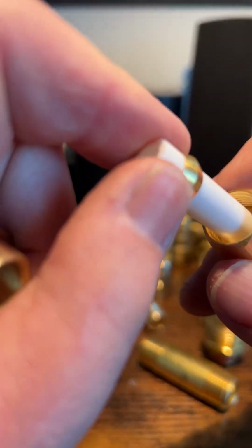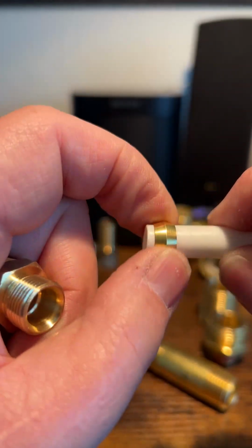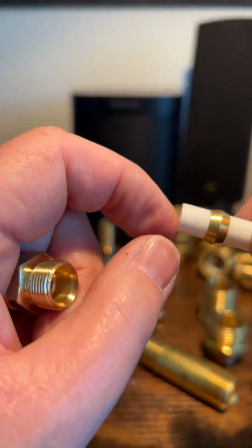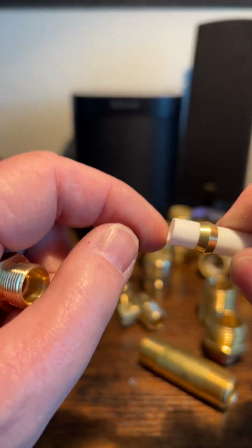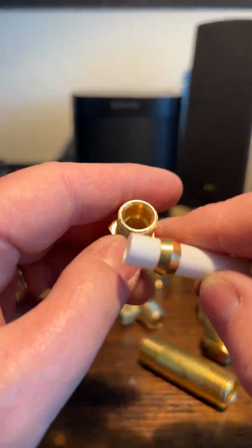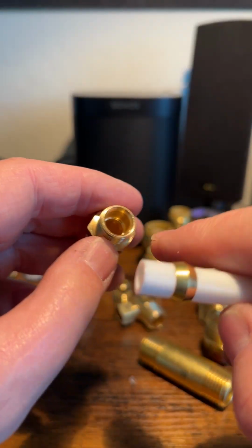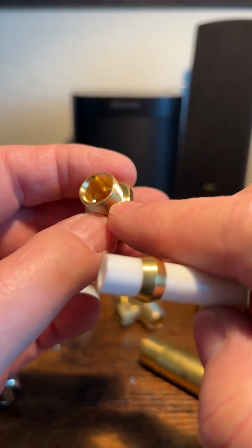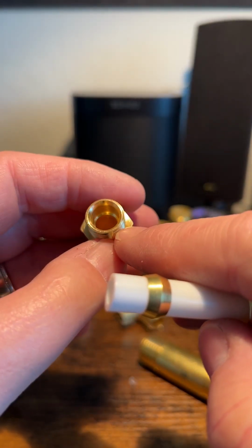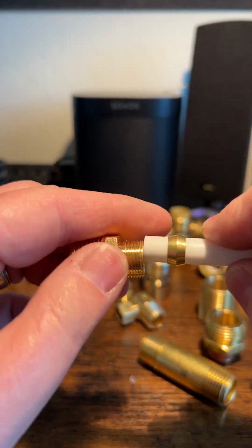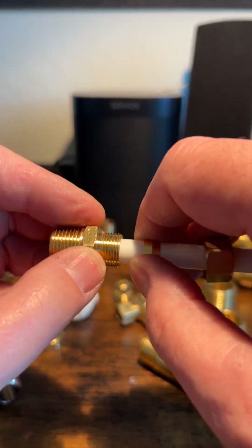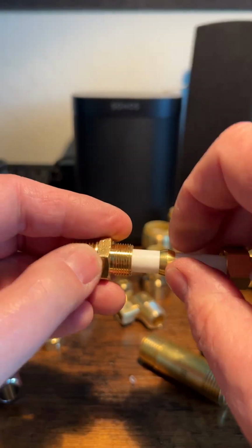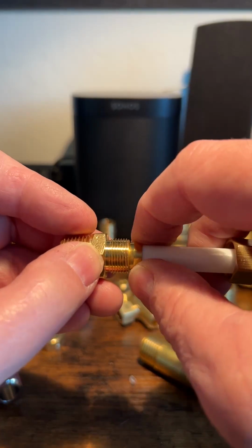And this is your nut, and it fits on there nice and tight, right? And then you want to make sure that this edge is nice and flat. If you look inside a compression fitting, you're going to see a stop inside there, and that's where the pipe sits. That's the seat for the pipe. So make sure that hits all the way down to the bottom. And this is going to push inside there.